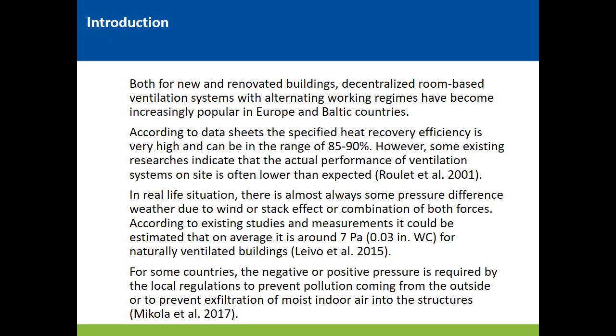There are different possibilities for ventilation systems, but lately there have been more and more cases when people choose to place local decentralized ventilation systems because they are small and easy to install. You can place them both in new buildings and in renovations, and according to the manufacturer data sheets, they guarantee a very high heat recovery efficiency, up to 90%. But there is a little problem, because there isn't one specific way to determine this efficiency, and the manufacturers may be manipulating this data a little bit.